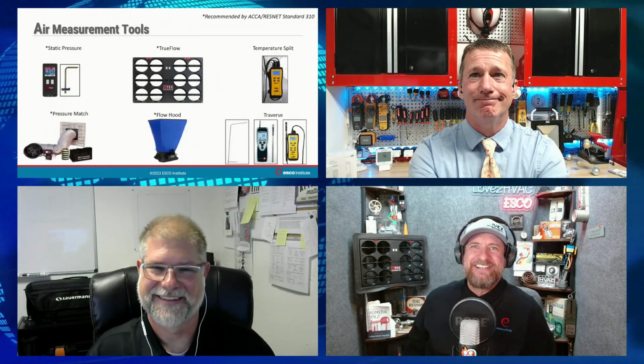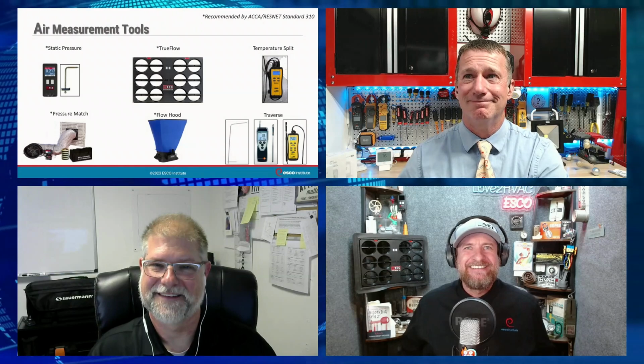I thought I was doing some great ductwork. I thought my ductwork was better than most people around me, but it still wasn't right because I wasn't testing it. It was better, but it still wasn't right. So it was like less wrong. When I started testing properly, I got to see that if I actually do these calculations, I can have properly performing systems. And then I found out I could use smaller systems and have happier customers with lower humidity.